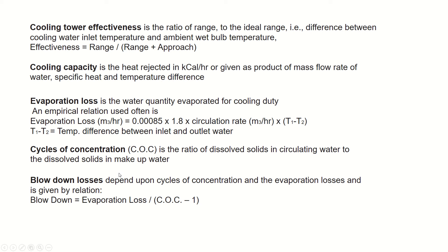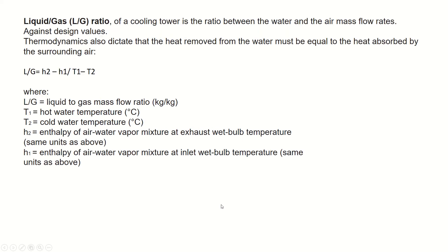Blowdown is done to maintain the level of TDS in a cooling tower. The loss due to blowdown is calculated using cycles of concentration: blowdown equals evaporation loss divided by (cycles of concentration minus one).